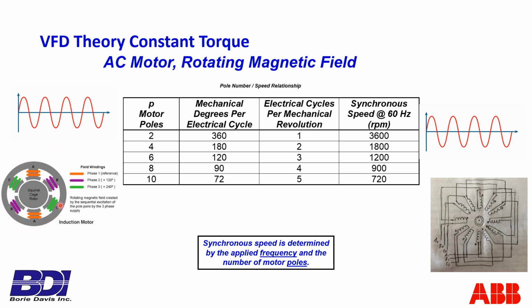Now this is a simplified stator in a motor showing 3 phases, phase A with 2 poles, B with 2 poles, and C with 2 poles. So this is a simple 2-pole motor, 2 poles per phase, A, B, and C. If this is the waveform for phase A being applied to the stator, then during the positive alternation here, A will be positive relative to A naught, let's call it, on the bottom pole. That would cause the magnetic field to move around the stator from here to here. On the negative alternation, this pole becomes positive and this pole negative, and that would continue to pull the rotor around this way. So for one cycle of input, one positive alternation and one negative, we get one revolution of the motor.